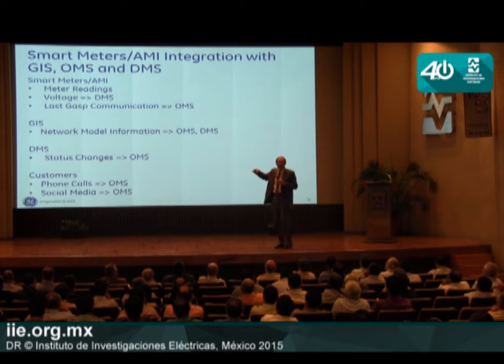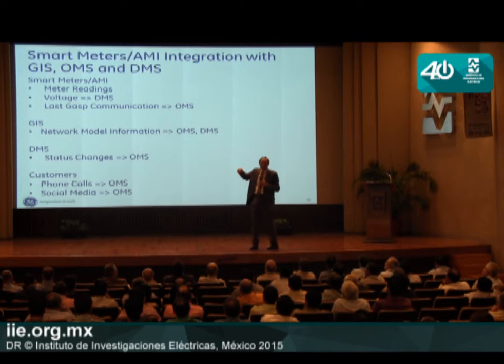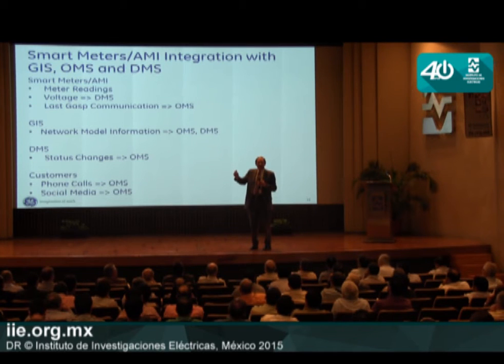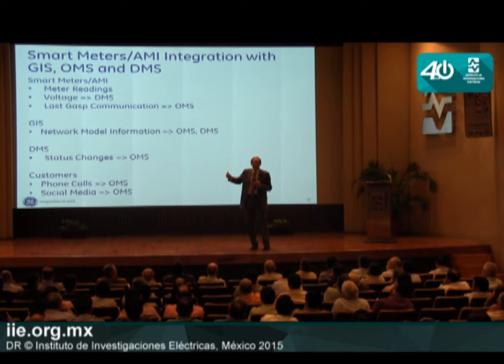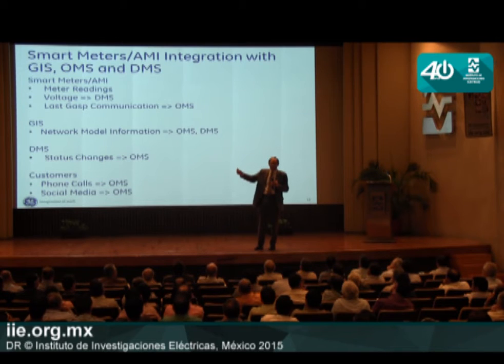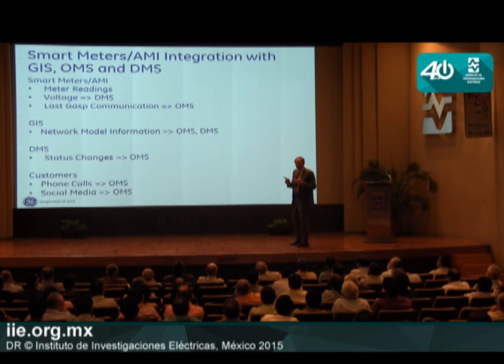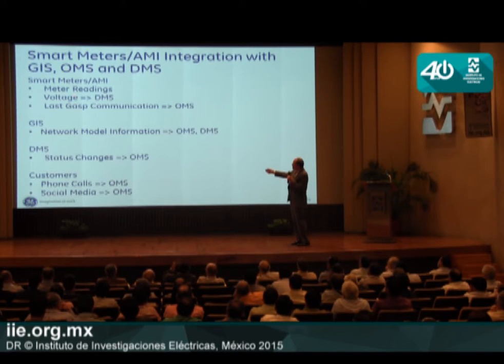I don't know what it is in Mexico, but in the United States we have an American National Standard, ANSI standard, that says the voltage delivered at the customer site must be 120 plus or minus 5%. So it must be between 114 volts and 126 volts by law, okay? So I need to know what is the voltage near the end of a feeder, a long feeder with a lot of voltage drop. And I can use smart meters, certain smart meters, for that.